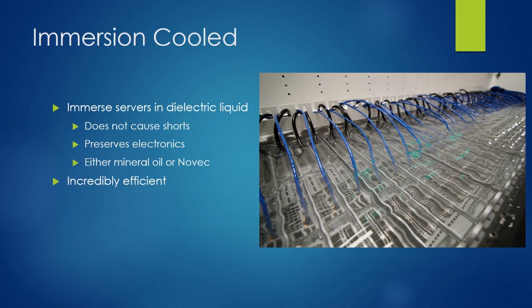There's more than one way to do it. This is mineral oil, but there's also a product called 3M Novec, basically a fire suppression liquid you can immerse things in. It can be even more efficient than direct water cooling because the system is so simple—you're just dumping cooler liquid in and taking it out, and the temperature delta only needs to be a couple degrees because of the liquid's specific heat capacity. You can fit so much more heat into the same volume, so it really is a good system.